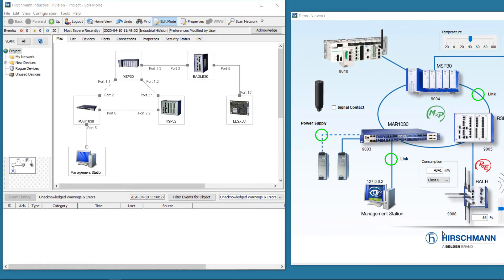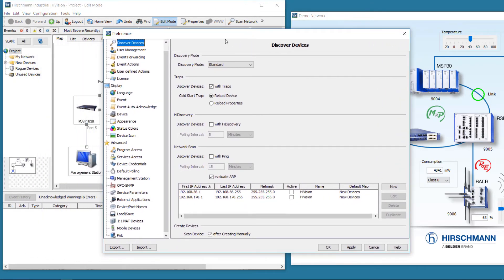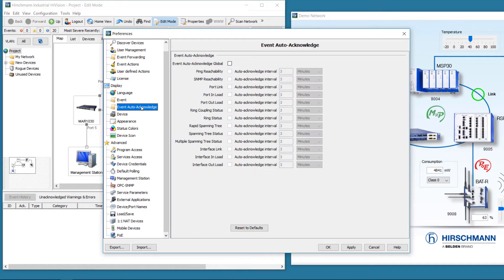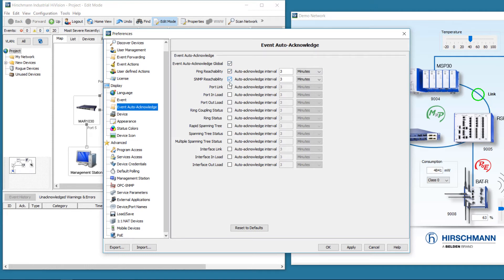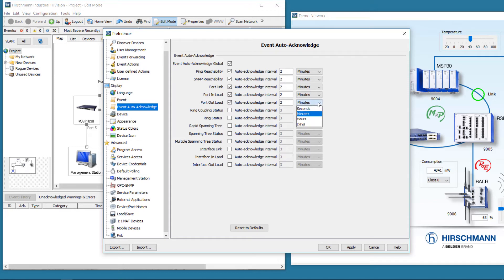The event auto-acknowledge function is located under the Preferences Display menu. Here you can select which events should be acknowledged automatically. These are events which indicate a change of network topology. You must also select the time within which the events must be rectified in order for the event to be acknowledged automatically. Events which exceed this duration will not be acknowledged. The event duration can be configured from seconds to days.